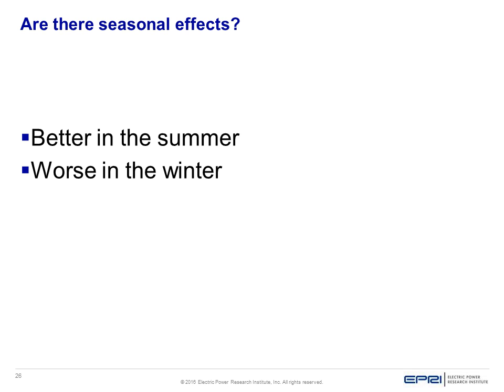If you have a lot of electric load in the winter, that load is normally controlled by a thermostat. Even an electric heater is just a resistor, highly sensitive to voltage, but if it's temperature controlled, lowering the voltage just makes the heater run longer to make up for it. So overall there's less benefit in the winter than in the summer.